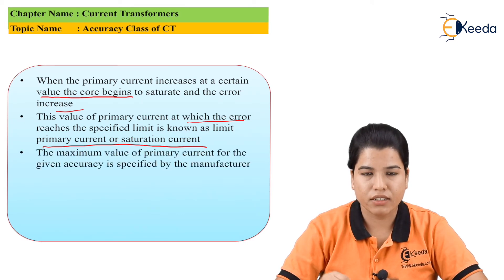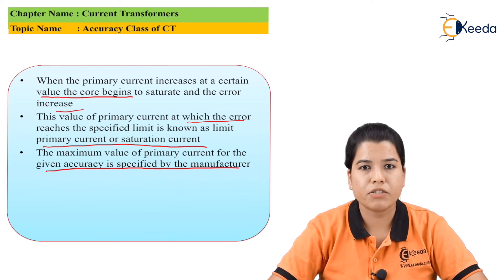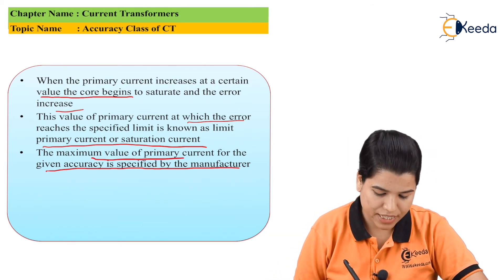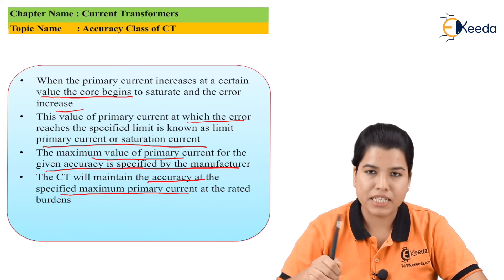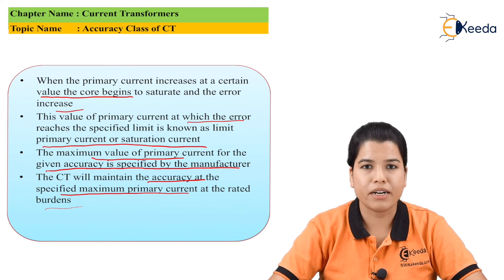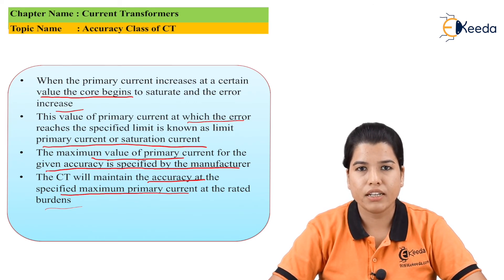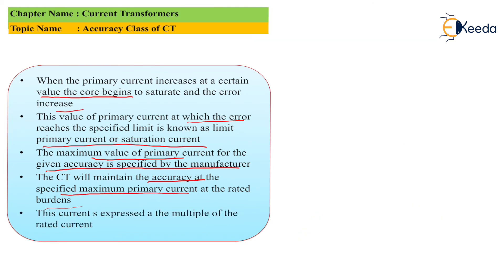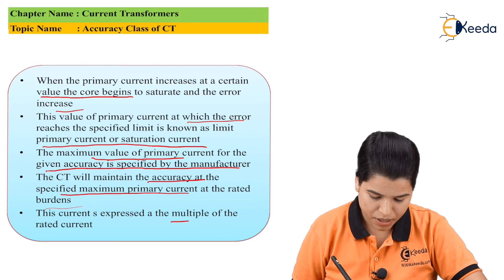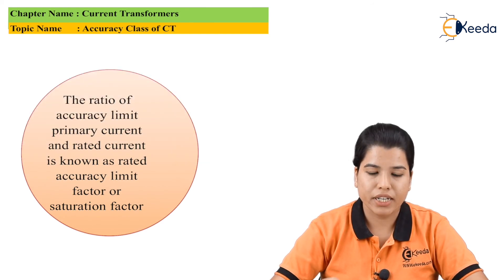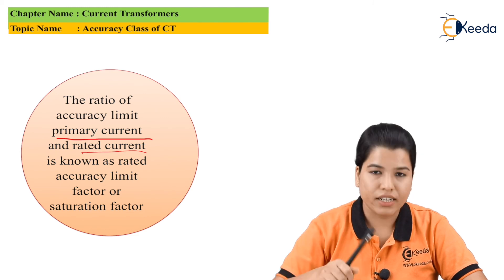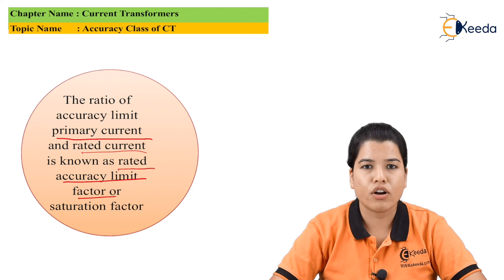The maximum value of primary current for the given accuracy class is always specified by the manufacturer. While designing the CT, the manufacturer will mention the value of maximum primary current. The CT will maintain accuracy at the specified maximum primary current at the rated burden. Whenever there is a load — that is burden — on the CT, the CT will try to maintain this rated primary current as specified by the manufacturer. This current is expressed in multiples of the rated current. The ratio of accuracy limit primary current to the rated current is known as the rated accuracy limit factor or the saturation factor.